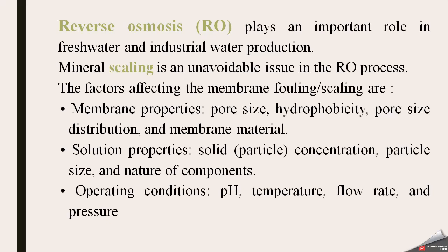Third, a very important thing is the operating conditions, that is the pH of the water, the temperature at which we are carrying out the filtration, flow rate, and the pressure applied across the membrane. So these are the important factors which affect the process of fouling and scaling. When we develop any of the techniques to control the scale, we have to consider these factors, and after considering these three important factors, we will develop the techniques to control the scales.